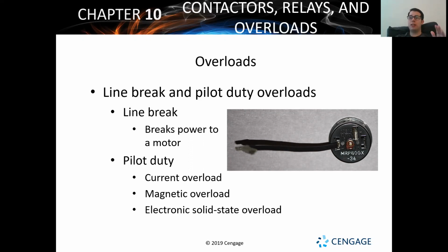And then electronic solid states, these are going to be more of your electronic sensor controls and control board controls that will actually choose when to turn on and off that system for various reasons, whether for a time delay relay or for a temperature delay, whatever it might be. Typically the most common one for electronic solid state is for heat pumps. Compressors will stay off for a certain amount of time to allow for the system to balance its refrigerant back to where it needs to be, especially with that reversing valve, which you guys will learn about operating on a heat pump. So you'll see those used a lot for those.